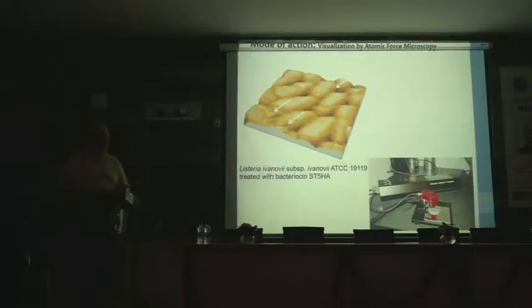Again, it's not cheap, and the problem is that it needs to be in a place where there is no vibration. Because imagine I have the microscope here on the table and I just come and touch the table, you lose the image. It's very sensitive. Normally, we need to put it in an underground place with a solid concrete table so there is no movement. There was even a joke: at one university a metro was passing nearby, and they said, no, we cannot. Because you don't feel the vibration of the metro, but the equipment feels this vibration.